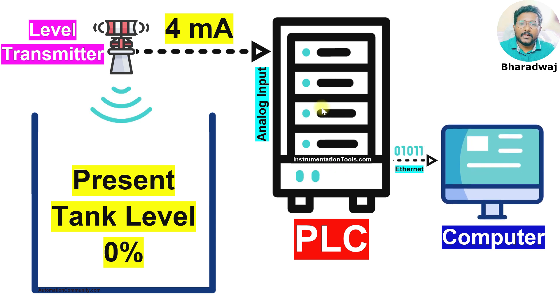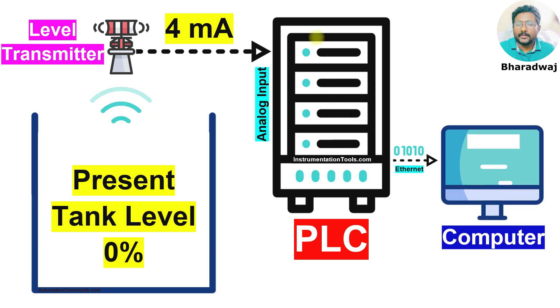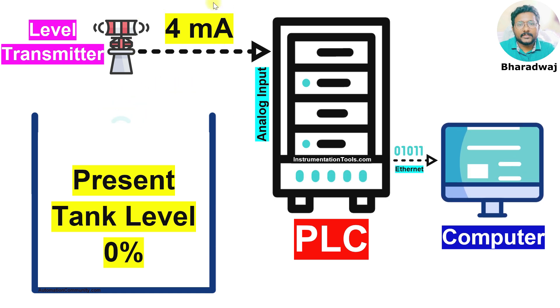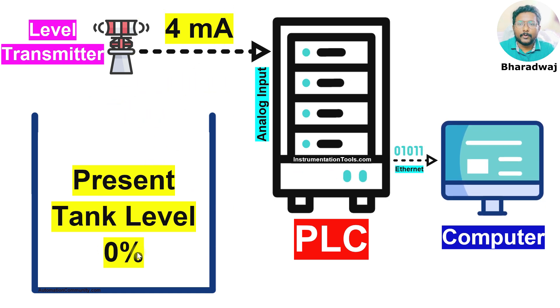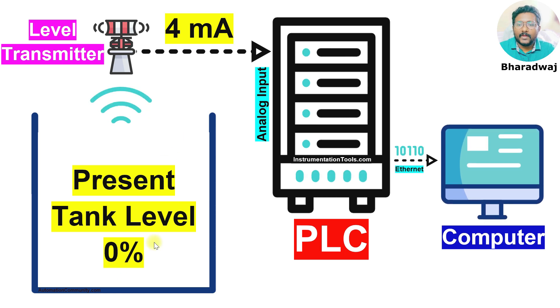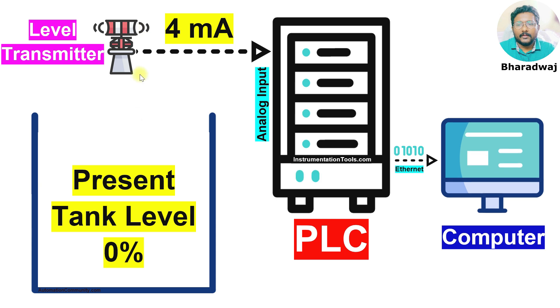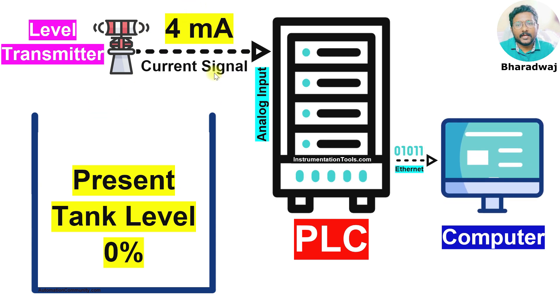The current range is 4 to 20 mA. The 4 mA represents the 0% signal of the process variable. That is why when the tank level is 0%, the transmitter is sending a 4 mA current signal to the PLC.